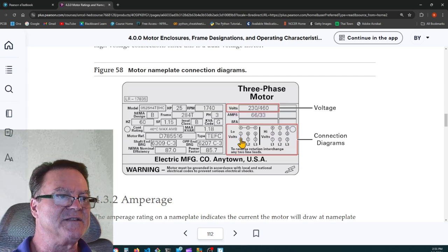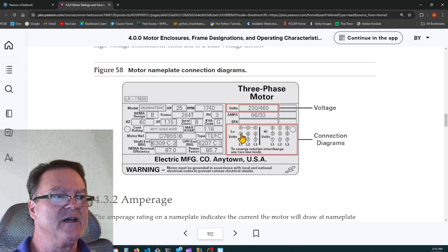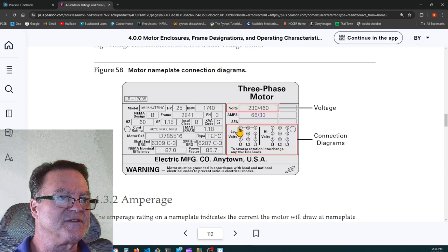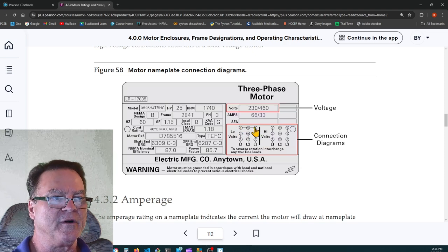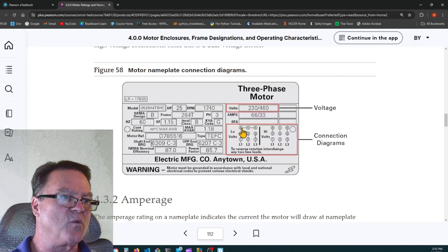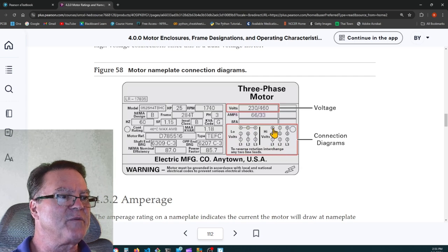This is the 9 leads in the casing. 1 to 7, 2 to 8, 3 to 9. Tie 4, 5, and 6 together. I can tell you right away that this is a Y wired motor between delta and Y. This one's wired Y because we're hooking 4, 5, and 6 together. And if we wanted to put it in high voltage, we'd put 4 to 7, 5 to 8, 6 to 9, and 1, 2, and 3 are our leads out. We'd connect that to the incoming power.